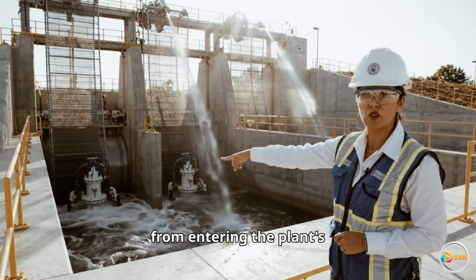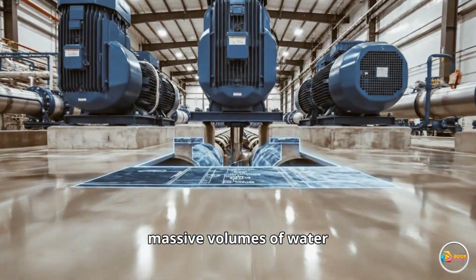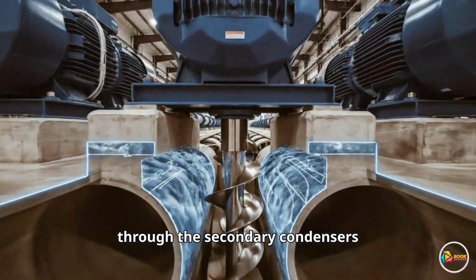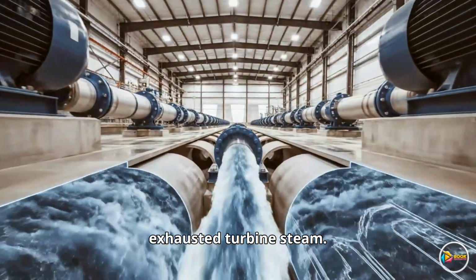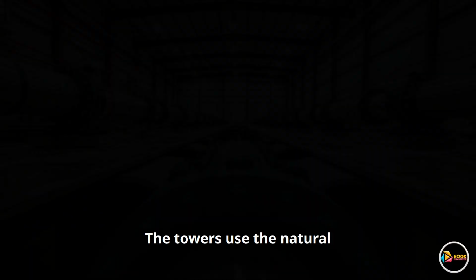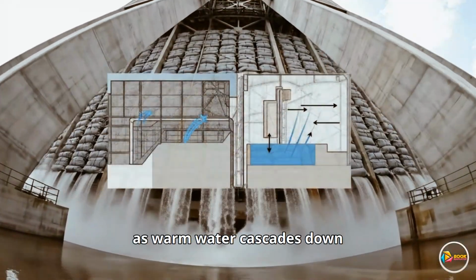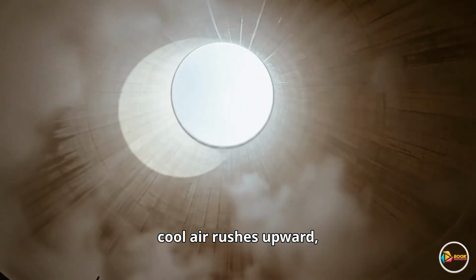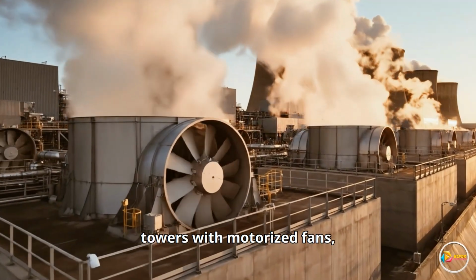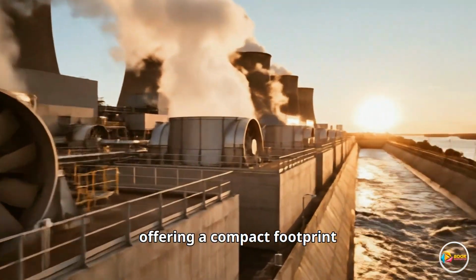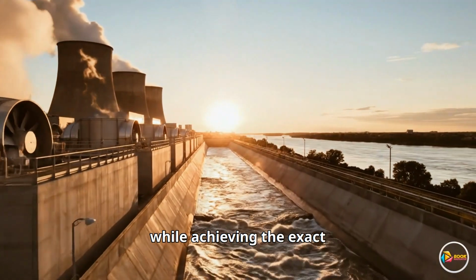These traveling screens prevent aquatic life and debris from entering the plant's cooling systems. Colossal pumps circulate massive volumes of water through the secondary condensers to cool and condense exhausted turbine steam. Natural draft towers use the natural chimney effect. As warm water cascades down over internal baffles, cool air rushes upward, naturally shedding heat without large fans. Other plants use mechanical draft towers with motorized fans, offering a compact footprint while achieving the exact same thermal heat rejection.